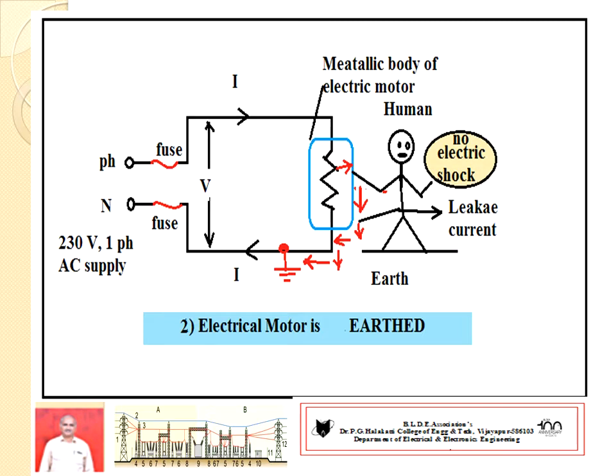Second case, if the same motor is earthed. So what happens? You see there. In this case also, if a live wire touches the metallic part, then a leakage current is developed. If a person touches that part of the motor, then the leakage current will flow to the earth point. It is not flowing through the human. Hence, the operator or human is free from electric shock. This is the importance.